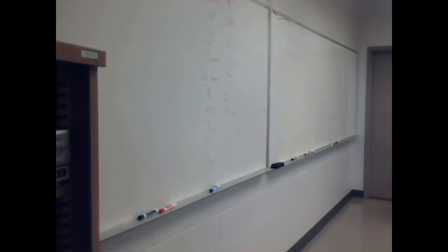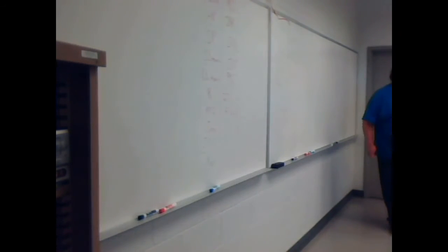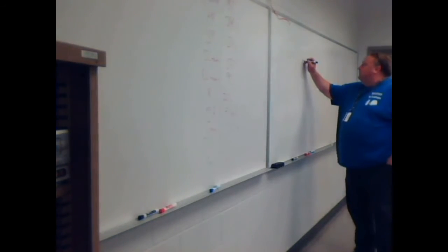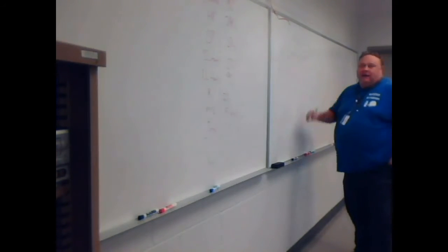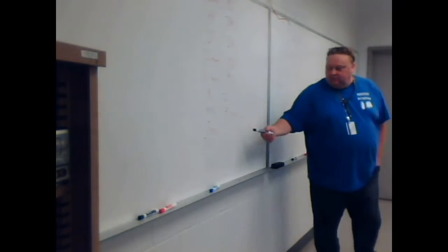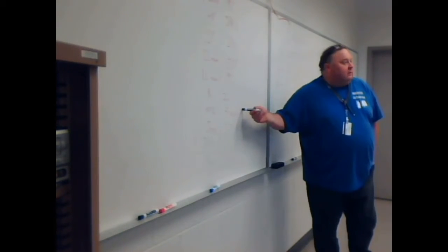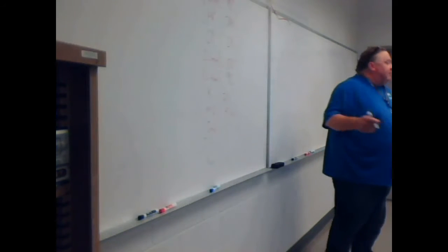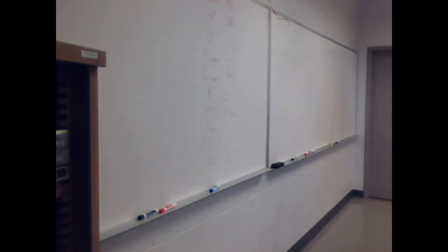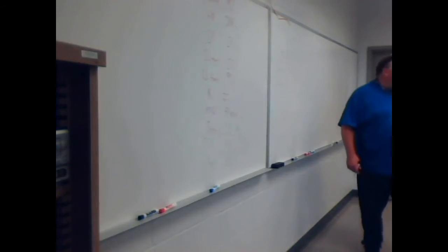But getting back to this, superheat. What did I say our target was on superheat? 5 to 12. And I said it only matters if what? If I've got a fixed metering device, right? Because if I've got a TXV, superheat isn't going to help.